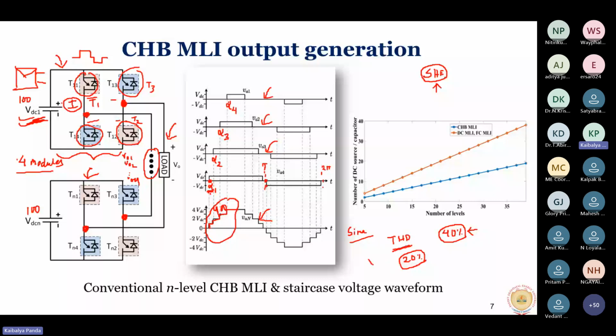Why not current THD? Because in this case, if the load is, let us say, an RL inductive type load, you will automatically get a current pattern that lags behind the voltage, so you'll get a current pattern generally in sinusoidal form. By changing the load pattern, you are going to get a sinusoidal type of current. So I am more concerned about the voltage THD, which is now coming to approximately 20%.